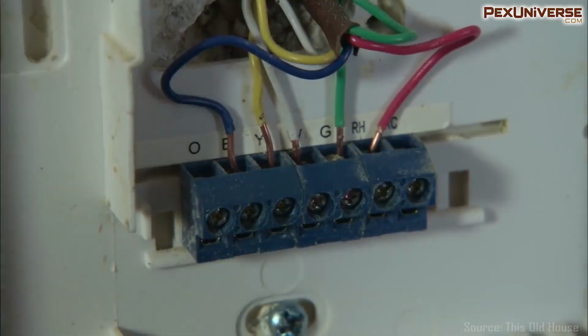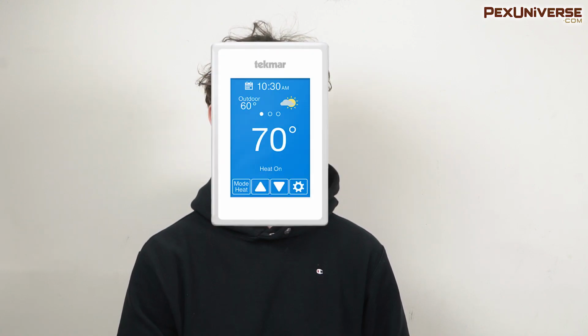Red or RC wires are responsible for the 24-volt power connected to your transformer. Dual transformer systems also make up for cooling and heating systems. These RC wires only, however, connect to your cooling system. The RH wire, also known as the H wire, is also a red wire and also connects to a 24-volt power source. So the RH wire only connects to your heating system, as opposed to the cooling system like the RC wires. Lastly, we have the blue wire, known as the C wire, C standing for common wire. It is only used for smart thermostats.